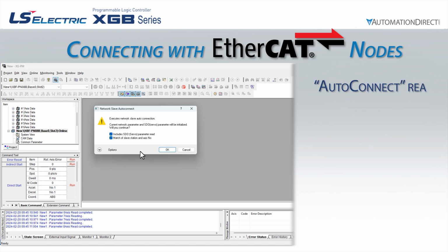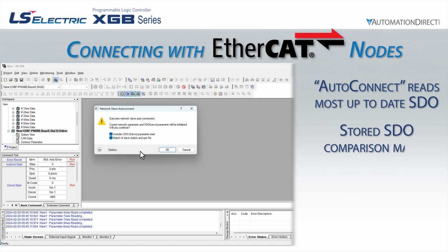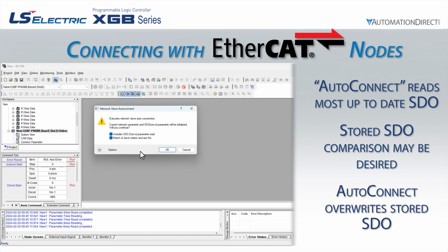While AutoConnect reads the most current SDO information directly from the nodes, at times it is useful to compare the SDOs stored in the motion module and the current SDOs in the drives to each other. The software gives the option to access both. Because AutoConnect overwrites the saved SDOs in the motion module and software, you will need to save an offline copy of your XGPM project prior to executing the AutoConnect if you want to compare the files.